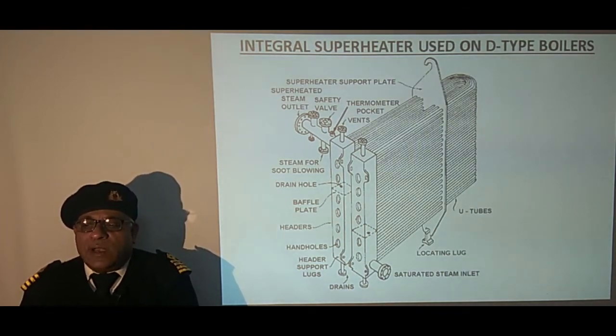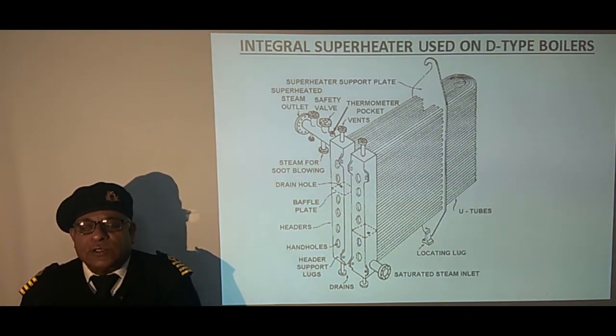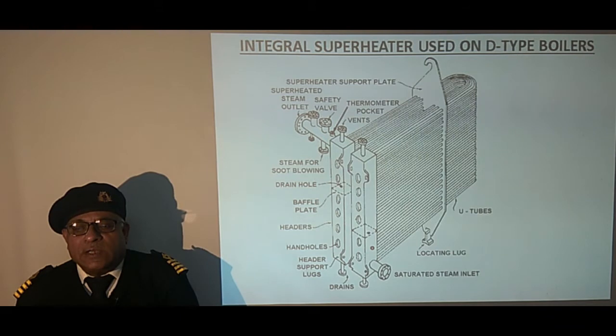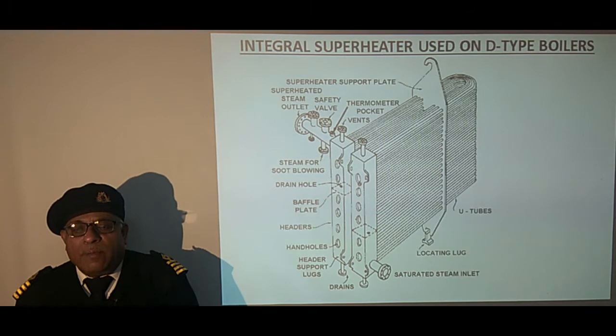It consists of two headers to which U-tubes are attached. Each header is equipped with a baffle plate, due to which steam takes three passes through the flue gas passage before it leaves the superheater. The steam enters from the inlet connection, takes a pass to the outlet header, then goes up through the upper tubes, comes back to the inlet header, and finally goes out from the outlet pipe.